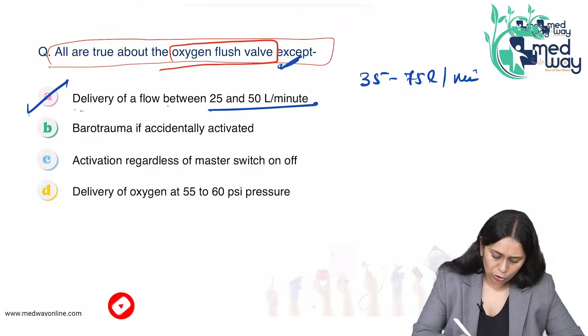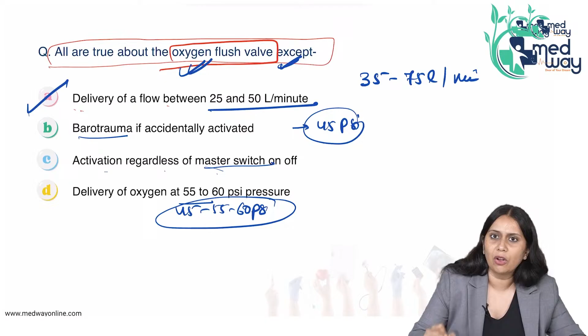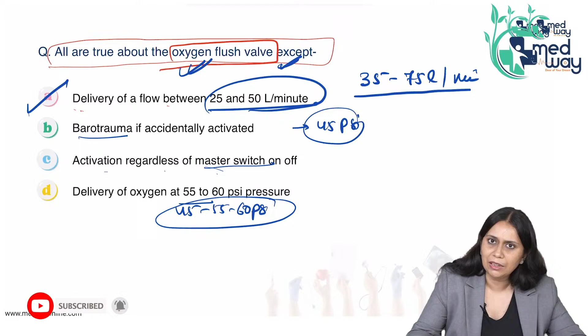Activation regardless of the master switch on or off. So, this emergency oxygen flush is independent of the electrical supply, the master switch. We can press the flush even in the absence of electricity, it will operate. So, activation regardless of the master switch on and off, this is true. Then delivery of oxygen at a pressure of 45 to 60 psi. This is the pressure at which the oxygen is delivered. So, this is also true. So, the first one is incorrect. We need to remember 35 to 75 liter per minute of oxygen it will deliver. Okay. So, this is important.